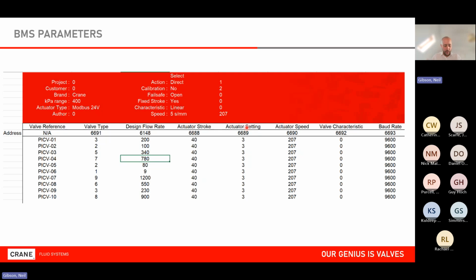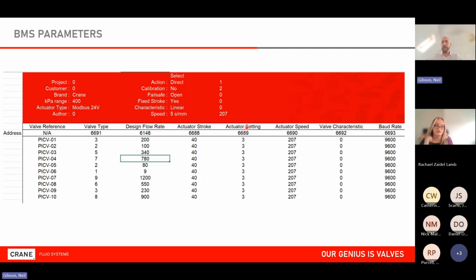So the way it works is we deliver the valves and we test all of the valves at the full stroke, which in this case is 4mm. So the valve arrives at fully 100% open and should not be turned. You shouldn't touch it at that point. The actuator is put on, and when you input the flow rate, it adjusts for the new valve stroke. So a very simple example is if at full stroke the flow rate is 0.2 liters a second, and the design is 0.1, it will change the stroke from 4 to 2 mil. And it will drive the 0 to 100% command from that new point. So it will drive to the positional flow rate on the stem. So it will adjust the stem stroke, and it completes a calibration every time you do that as well.